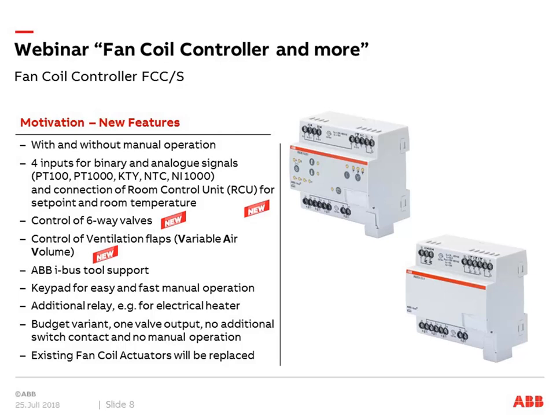As with all our new components, these are supported by the ABB i-bus tool, for testing and operating functions, viewing status information, and simulating situations for maintenance or commissioning. The keypad for menu operation is available, and the additional relay can be connected on the upper right side — as we had in our fan coil actuators before. For example, you can use it for operation of an electrical heater together with a fan inside. It's a freely programmable switch output additionally available.